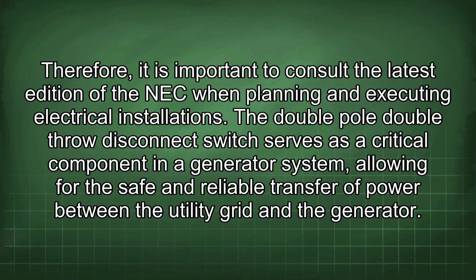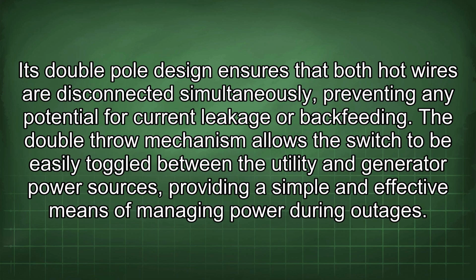The double-pole double-throw disconnect switch serves as a critical component in a generator system, allowing for the safe and reliable transfer of power between the utility grid and the generator. Its double-pole design ensures that both hot wires are disconnected simultaneously, preventing any potential for current leakage or backfeeding. The double-throw mechanism allows the switch to be easily toggled between the utility and generator power sources, providing a simple and effective means of managing power during outages.